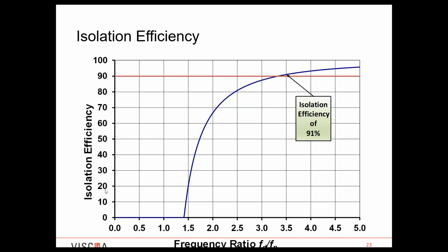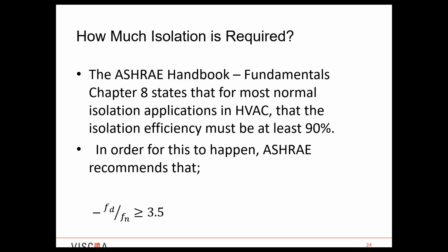Okay, so we've discussed this isolation efficiency curve pretty thoroughly here. So really, how much isolation is required? The ASHRAE Handbook Fundamentals Chapter 8 states that for most normal isolation applications in HVAC, the isolation efficiency must be at least 90%. So in order for this to happen, ASHRAE recommends that we're greater than or equal to 3.5 for our driving or disturbing frequency in the numerator compared to the natural frequency in the denominator.